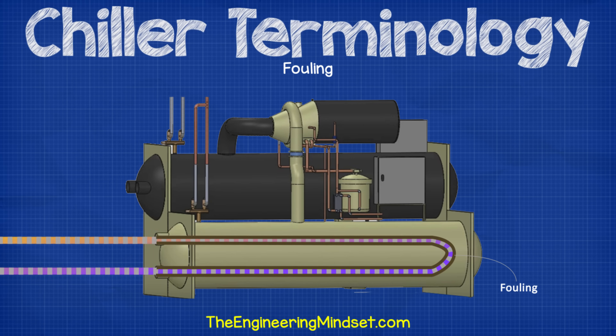Fouling. This refers to the buildup of dirt and organic substances on the surface of heat exchangers, which effectively insulates the surfaces and reduces the heat exchangers' ability to transfer heat. This is very common in the condenser of a water-cooled chiller because of the open circuit, which permits dirt and bacteria to enter the pipework. Good water treatment and monitoring over time should be implemented to reduce this. Chillers are designed to withstand a certain amount of fouling under normal operating conditions, but if this is exceeded, then the chiller will be unable to reach its design capacity.